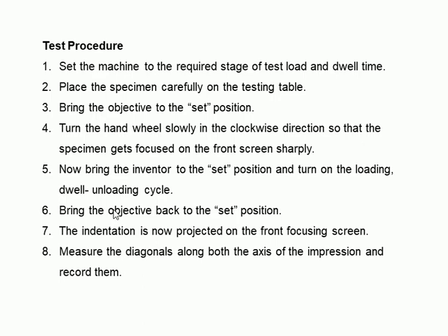Now bring the indenter to the set position and turn on the loading, dwell and unloading cycle. Bring the objective back to the set position. Then the indentation is projected on the front focusing screen. Measure the diagonals along both axes of the impression and record them.